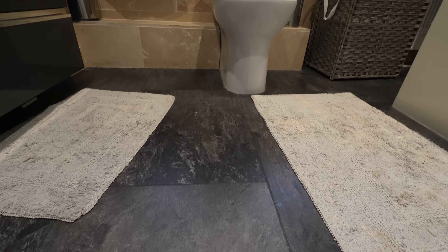I have been upstairs, but everything looks okay on the surface. It's mainly tiled with current flooring, so I don't really want to do any damage up there at the moment. And as there is a hole, what I'm thinking of doing is just sticking the inspection camera up and having a look to see if there's anything obvious. Hopefully we should be seeing some pipes with some signs of leak.